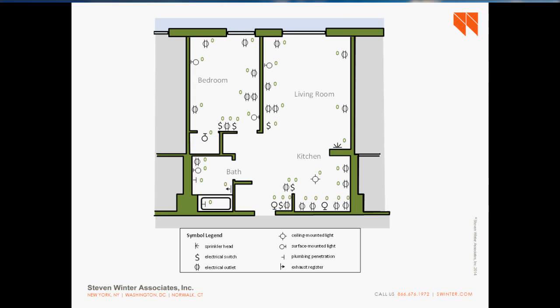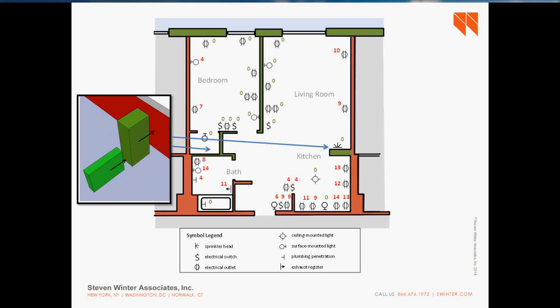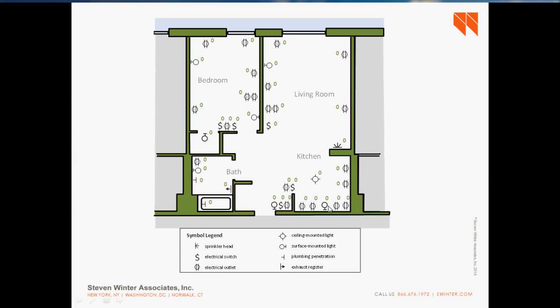After the aerosol, basically any leak that we could measure, we did measure, and couldn't measure any leakage. The instrument only goes down to about 2 CFM. There is probably some leakage coming from some of these, but if any, it's less than 2 CFM. That's pretty darn airtight. So it basically went from this much leakage to basically 0 pretty much everywhere.